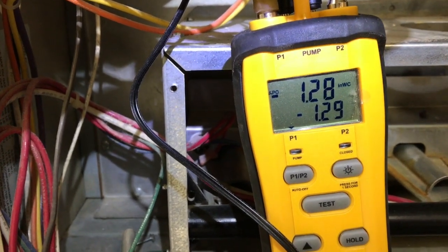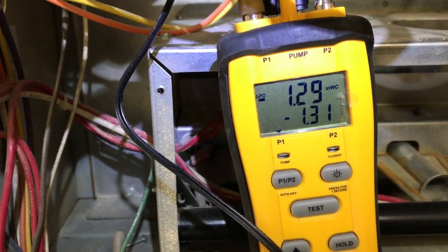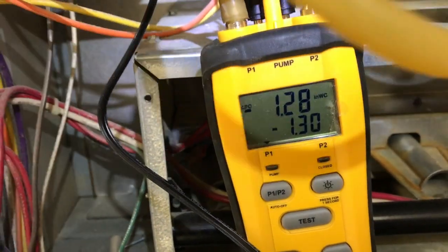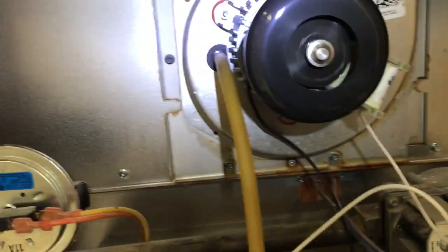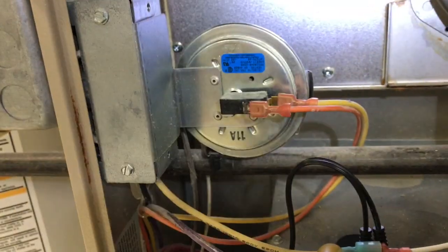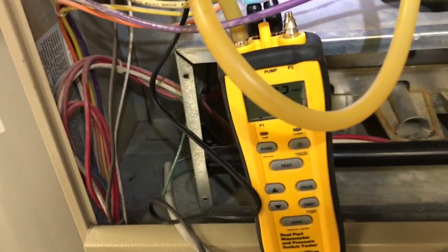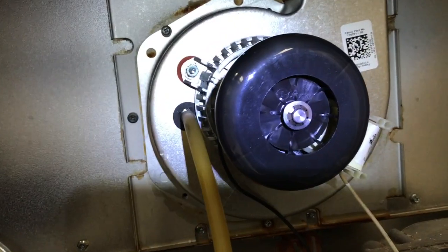Look at that, 1.27. 2.5 times what the old inducer was. So this is a good example of don't get tricked into just thinking you've got a bad pressure switch. Actually get out your test instruments and verify that your inducer motor is doing what it's supposed to do.